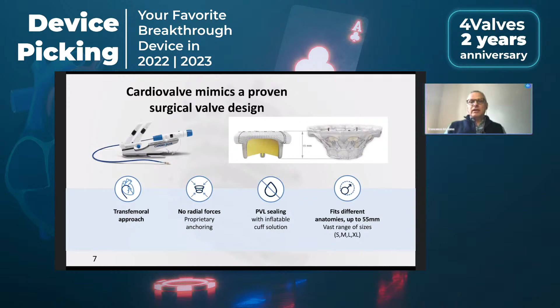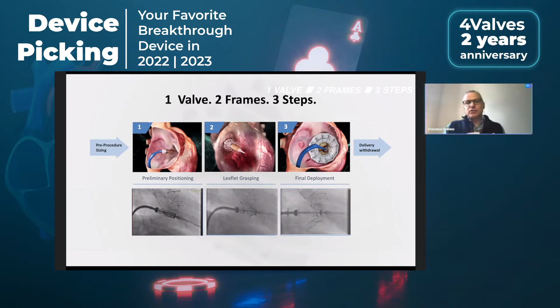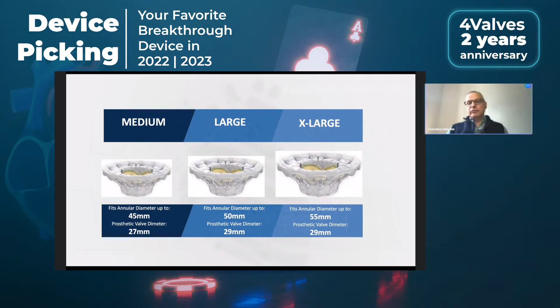Valve replacement in most occasions is a very simple concept. You get into the valve, in this particular case, you open some ventricular legs which are engaging the subvalvular apparatus. And after the subvalvular apparatus is engaged, just like you do with a MitraClip or with a TriClip or Pascal, where you engage two leaflets, here you engage the whole apparatus as much as you can. And finally, you release an atrial cuff. This device comes in different sizes and covers diameters at this moment up to 55 millimeters with a very large valve. It is a 29 millimeter diameter valve, which is important for tricuspid.